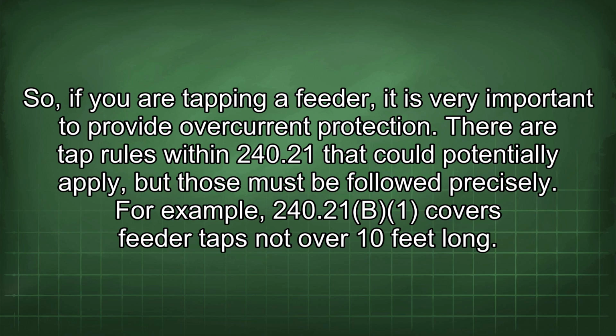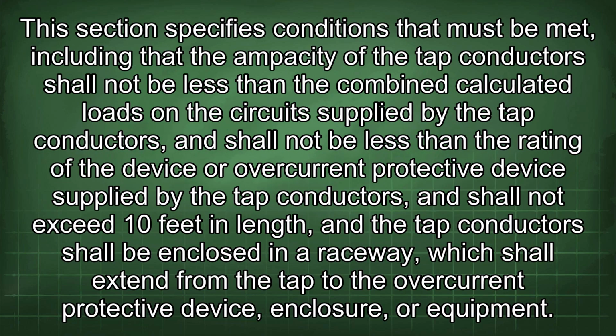There are tap rules within 240.21 that could potentially apply, but those must be followed precisely. For example, 240.21(B)(1) covers feeder taps not over 10 feet long. This section specifies conditions that must be met, including that the ampacity of the tap conductor shall not be less than the combined calculated loads on the circuit supplied by the tap conductors, and shall not be less than the rating of the device or overcurrent protective device supplied by the tap conductors, and shall not exceed 10 feet in length, and the tap conductor shall be enclosed in a raceway, which shall extend from the tap to the overcurrent protective device, enclosure, or equipment.